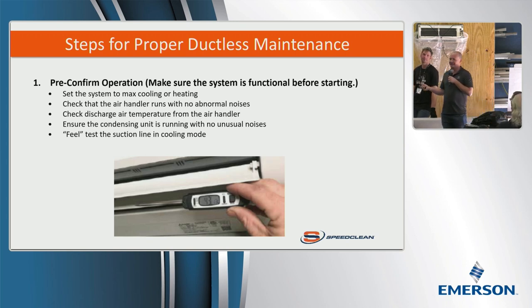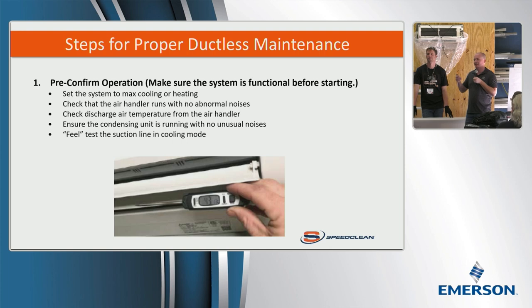It's because that's how it kind of dictates. It's really trying to hit a target coil temperature, so it ramps the compressor based on that. It's not completely fixed, there is some variance, but when you go to high speed, you're going to see it consistently. That's why you'll see really high delta Ts when you have high load. Now, there's a high and low limit to that. It's not like it's going to run a 40-degree delta T if it's 90 degrees inside the space. That's not going to happen. But you are going to see fairly consistent discharge temperatures when you're at set point, when the space is at temperature, I should say.